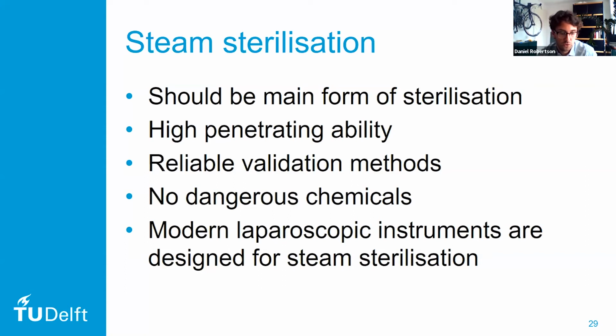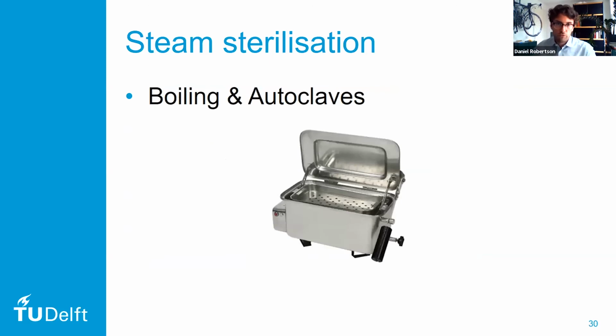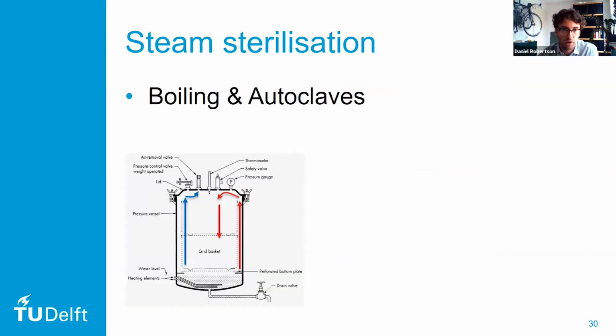And to clear up one misconception, modern laparoscopic instruments are generally designed for steam sterilization. You can check this by looking up the instructions for use of the manufacturer of your instrument. Now, instruments used to be boiled for sterilization, but this is no longer recommended because water only boils at 100 degrees Celsius, and this is not enough to sterilize the bacterial spores. So we need to increase the temperature of water, and how we do that is by using a closed chamber.